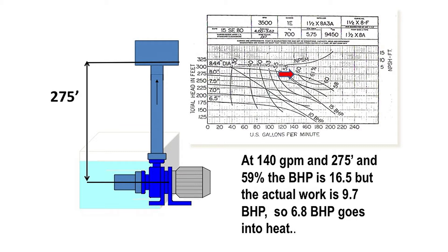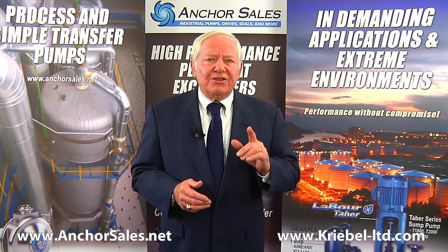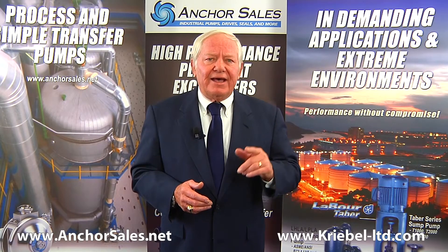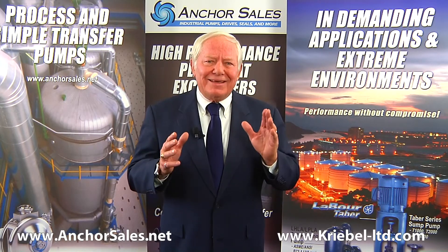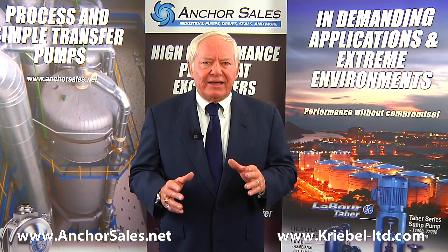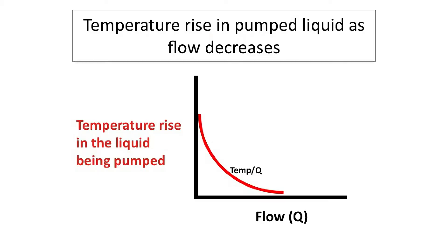That heat can be dissipated by radiation or convection from the pump casing, but the majority is removed by heating the liquid being pumped, increasing the temperature of the pumpage. As the flow decreases, the efficiency decreases, and a greater amount of heat per unit mass goes into the liquid, while there is less and less mass to remove the heat. This means the temperature rise across the pump increases asymptotically toward shutoff.